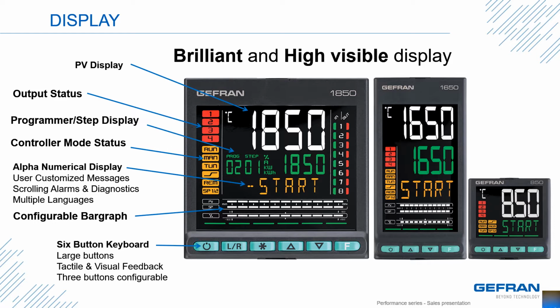Moving over into the green under the 1850 process display is the optional ramp and soak or programmer information along with the set point display. In yellow, we can view the status of the controller modes. This feedback to the user will let them see the controllers in run mode or manual mode, or maybe it's auto tuning or possibly in remote mode. Other functions include set point 1 and 2, and the set point ramp is running.